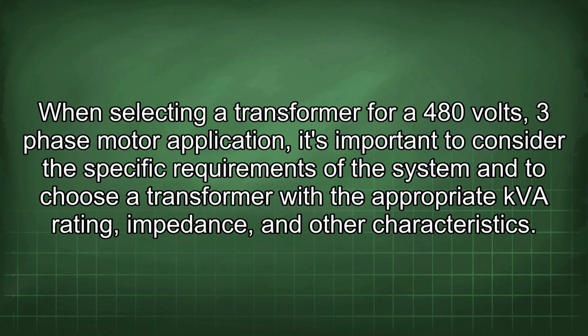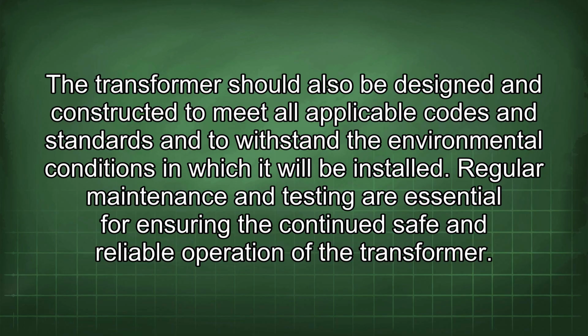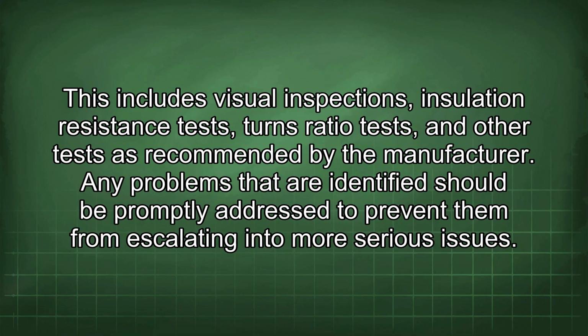When selecting a transformer for a 480 volts 3-phase motor application, it's important to consider the specific requirements of the system and to choose a transformer with the appropriate kVA rating, impedance, and other characteristics. The transformer should also be designed and constructed to meet all applicable codes and standards and to withstand the environmental conditions in which it will be installed. Regular maintenance and testing are essential for ensuring the continued safe and reliable operation of the transformer. This includes visual inspections, insulation resistance tests, turns ratio tests, and other tests as recommended by the manufacturer. Any problems that are identified should be promptly addressed to prevent them from escalating into more serious issues.